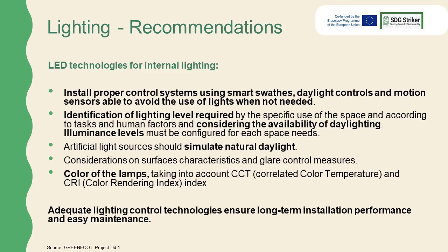For lighting design of interior spaces, the following points should be taken into consideration. Install proper control systems using smart switches, daylight controls, and motion sensors able to avoid the use of lights when not needed. Identification of lighting level is required by the specific use of the space and according to tasks and human factors, as well as considering the availability of daylighting.